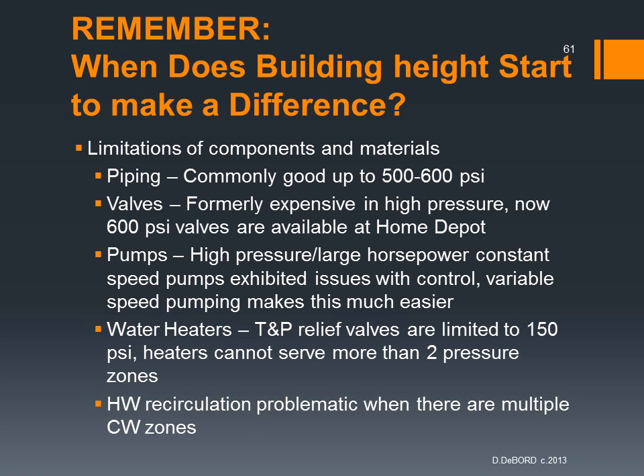So if you remember, we talked about when does a building height start to make a difference in your considerations. We have some typical limitations of components and materials, such as the piping, which is commonly 500 to 600 psi. The valves, it gets more expensive with the high pressure valves, but now you can even get 600 psi valves at Home Depot. That doesn't mean that they're the best quality. I'm not saying they're not good quality. I'm nothing against Home Depot. I'm just saying that you have to be careful with that stuff too.